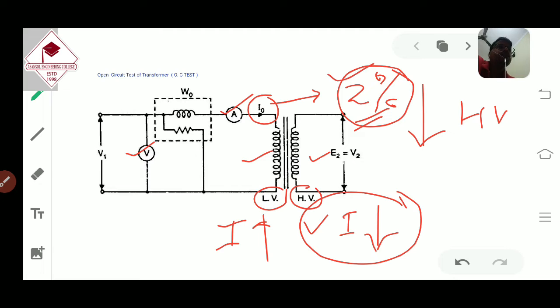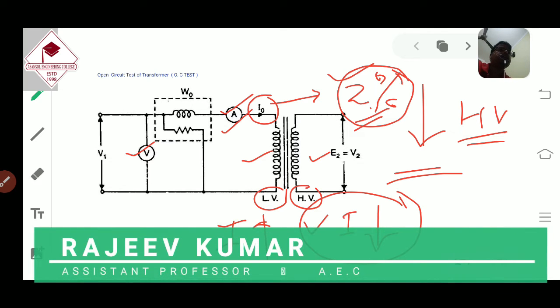So there are two factors lowering the current: already the no load current is 2%, and this current will reduce further if I connect the high voltage winding to the meters. It is very difficult to measure this very low current with an ammeter, because the ammeter precision is not too good.